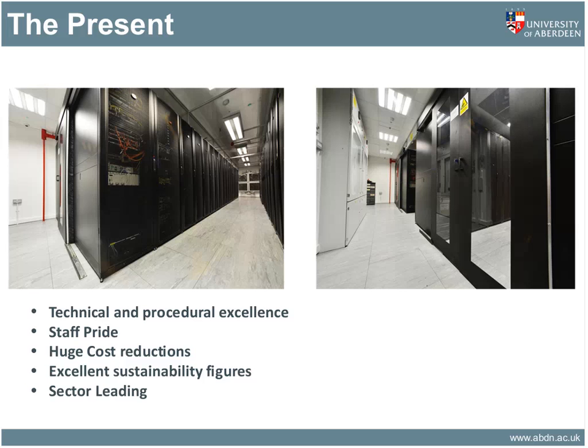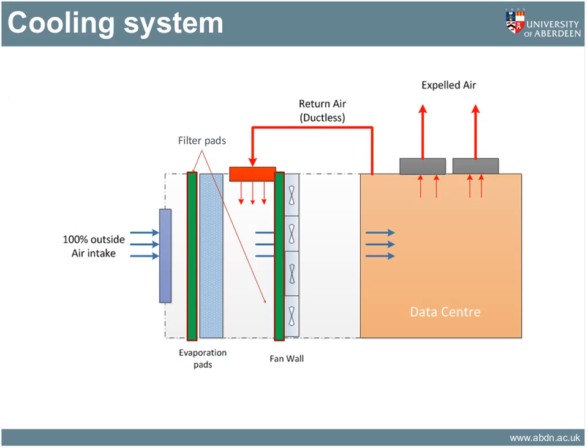One of the biggest success factors for us was the cooling mechanism we put in. We went with direct evaporative cooling. We take air in from the outside, filter it, and put it through evaporation pads when the temperature exceeds 20 degrees, which isn't very often in Aberdeen. We put it through another set of filters and then into a fan wall to give us a combined hot and cold aisle arrangement. Extreme caution and diligence is used when installing equipment within racks to make sure there are no gaps that would allow cold air to seep through.